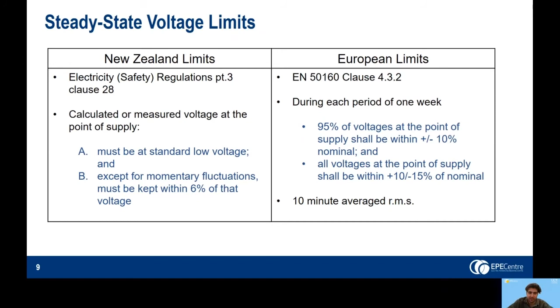There are 3 main differences between these and the limits used in New Zealand. Firstly, the tolerance is wider, extending to plus or minus 10%. Secondly, momentary is explicitly defined. And thirdly, there is an allowance for a small number of minor undervoltages while rejecting large undervoltages even when infrequent. In the following slides, I'm going to demonstrate how EV hosting capacity can be assessed using both the current New Zealand voltage limits and also a possible alternative, which, like the European limits, considers both magnitude and duration.